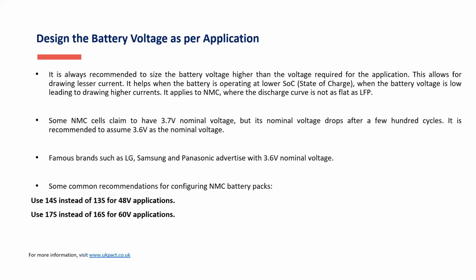It is always recommended to size the battery voltage higher than the voltage required for the application. This allows for drawing lesser current, and it helps when the battery is operating at lower SOC.